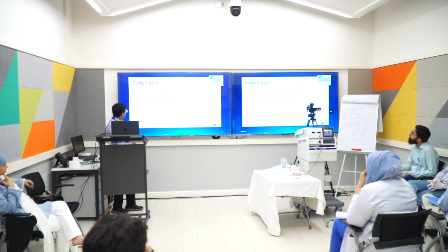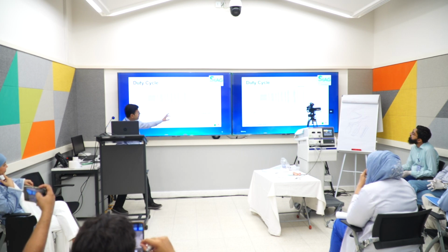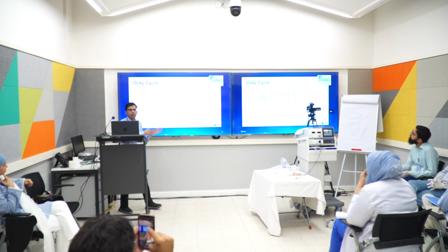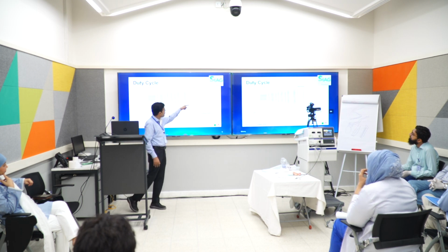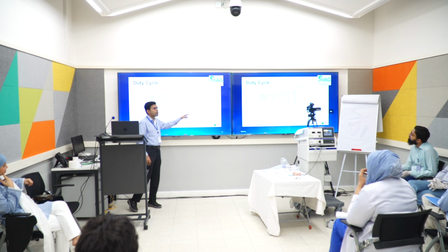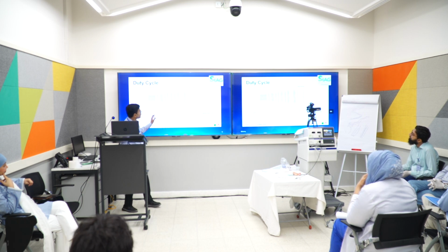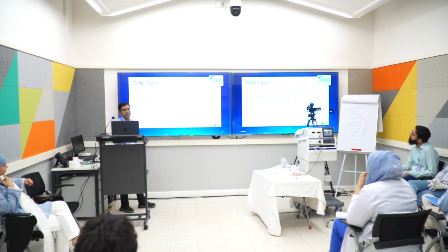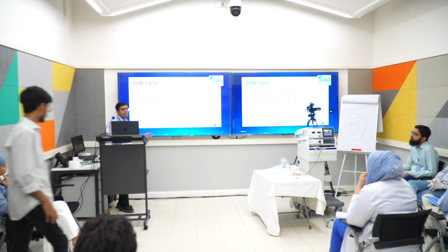So on one end we have cutting, and on the other we have coagulation. We saw the effect of voltage, right? Now we'll see the effect of cycle. Whenever there is continuous flow of the current, the technique will be pure cut. There is no interruption, you can see that. And if there is significant interruption between the two currents, the technique will be coagulation. So if you can see, the current flows during 6% of the cycle while coagulating, while in case of cut, it's uninterrupted throughout the cycle.